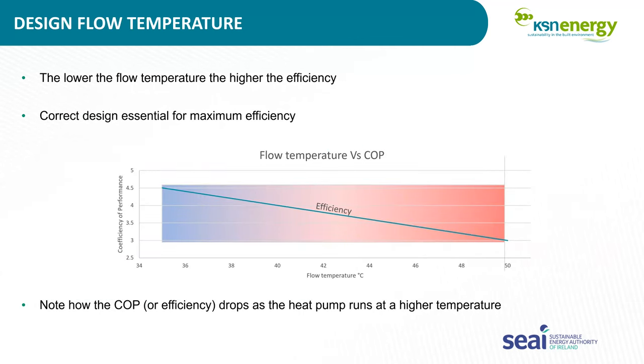The next thing is it's important to consider the working temperature when retrofitting a heat pump. We need to look at the efficiency. I don't know if it's difficult for people to see this graph, but as an example, on the left-hand side, the y-axis, the range goes from 2.5 to 5. Basically, the term efficiency isn't used when describing heat pumps. Coefficient of performance, or COP, is the term that industry uses to describe the efficiency.